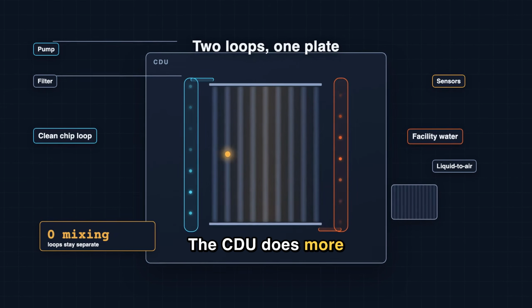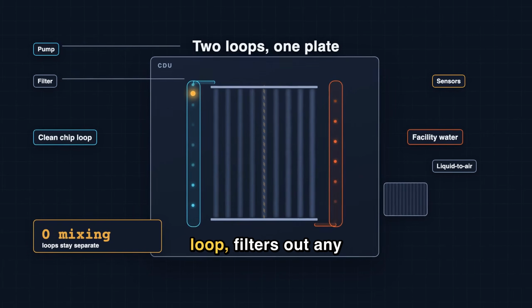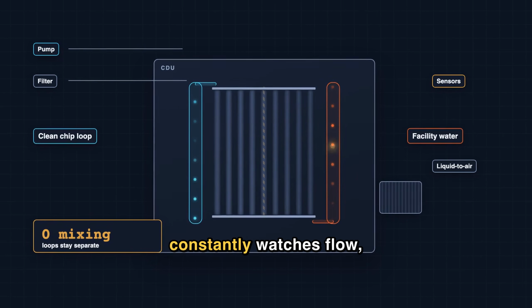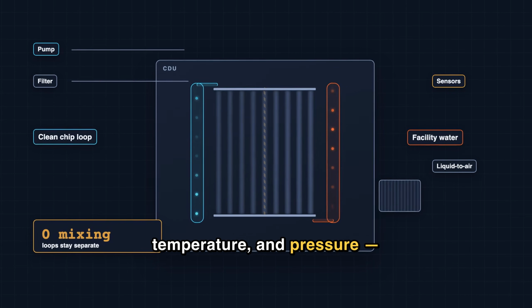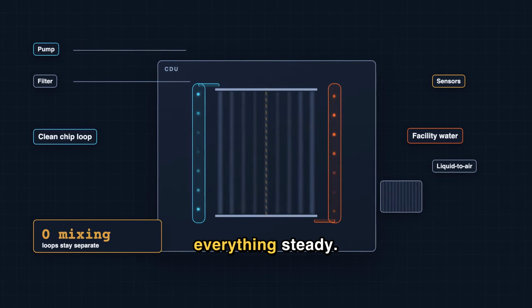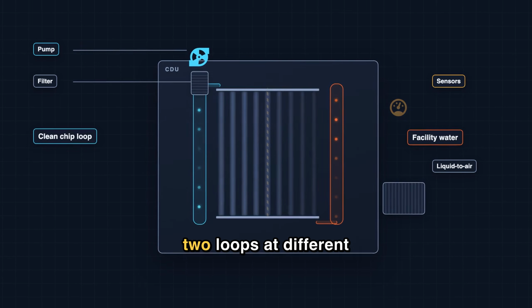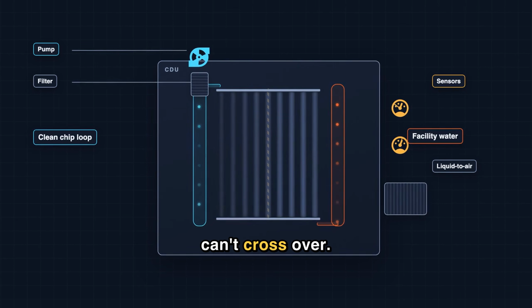The CDU does more than trade heat though. It pumps the clean loop, filters out any stray particles, and constantly watches flow, temperature, and pressure, dialing the pumps up or down to hold everything steady. It also keeps the 2 loops at different pressures, so a leak can't cross over.